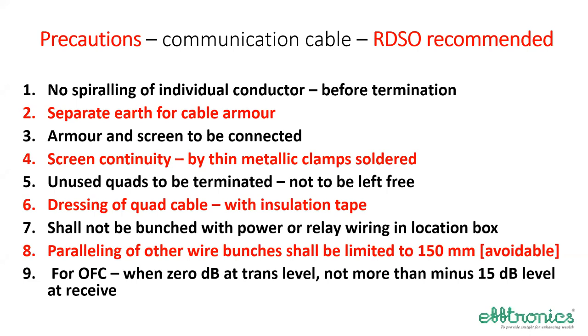Dressing of quad cable with insulation tape, because during maintenance, if it moves this way or that way, it will go nearer to the power supply wires. It shall not be bunched with power supply or relay wiring in a location box. Paralleling with other wire bunches shall be limited to just 150 mm, and if possible shall be avoided. In case OFC channels are used, there shall not be very high gain. It shall be up to a maximum of 0 dB. If you give it at one place, it shall not be more than minus 15 dB level at the receiver end.